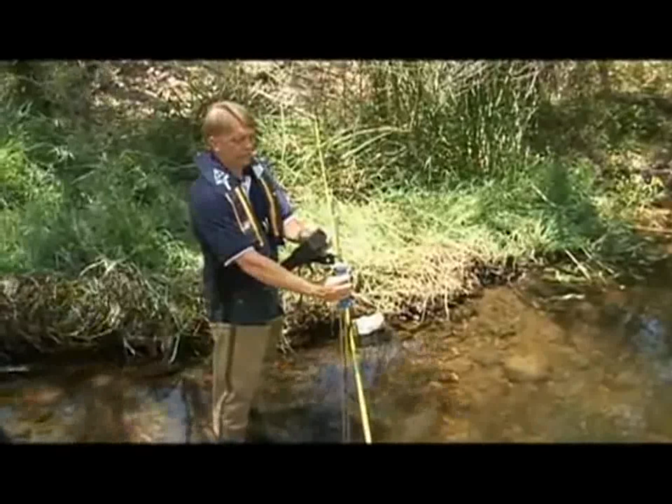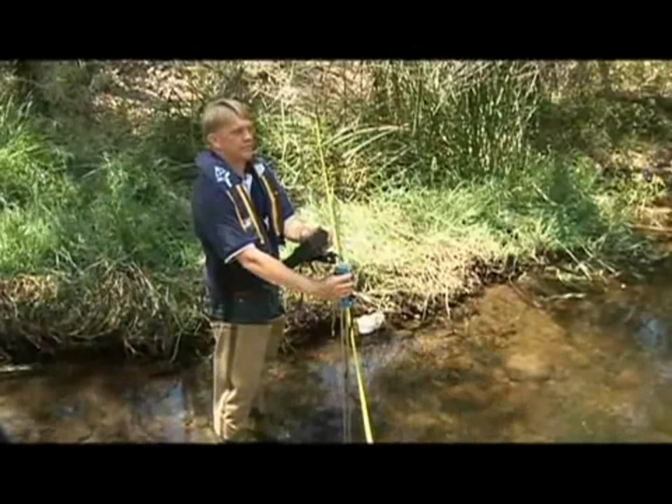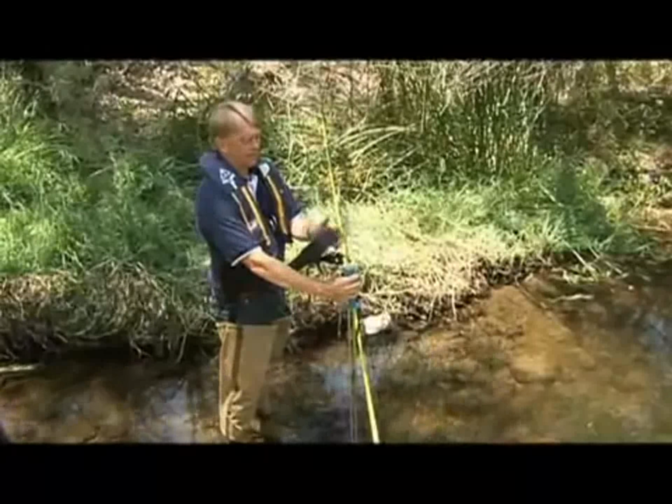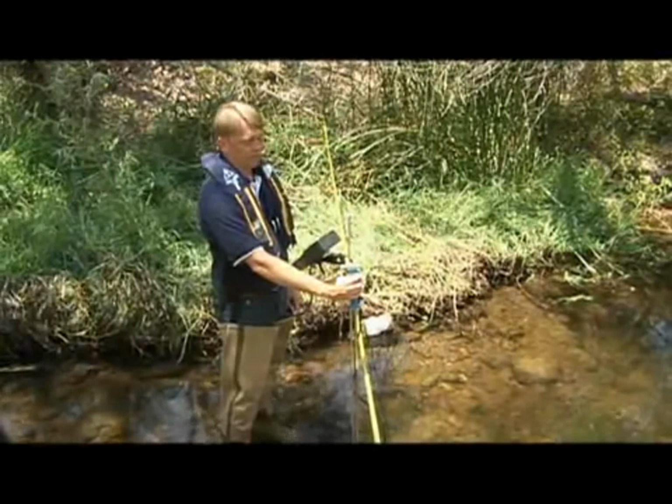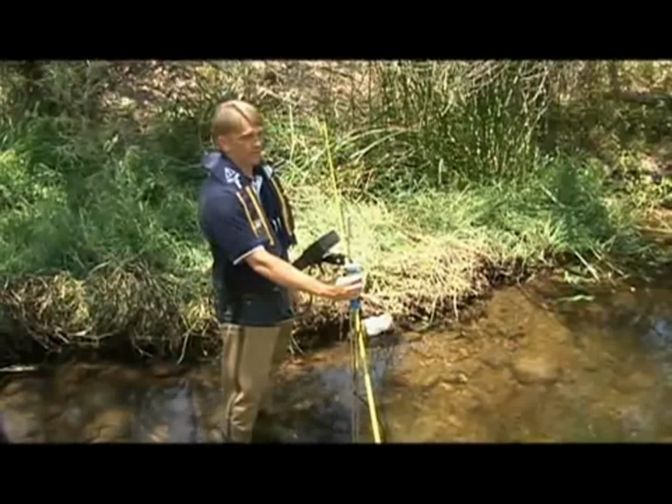The SNR values were a little bit higher. That's probably a function of being a little bit closer to the stream bed. The velocities were 0.007 meters per second with a variation of 0.001, or thousandths. So again, everything looks acceptable.